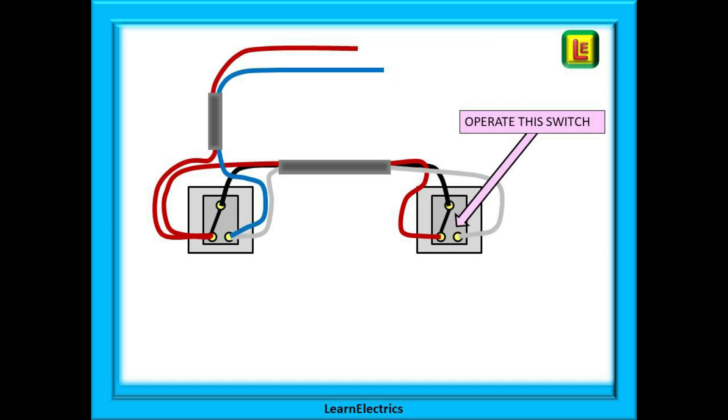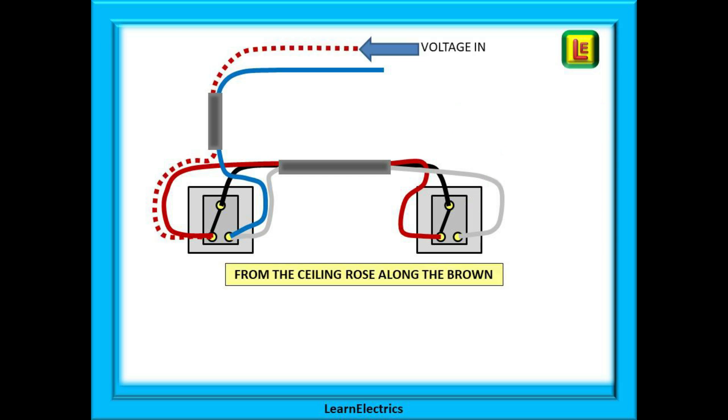If we operate the second switch, shown on the right here, what will happen to the voltage and the current flow? Voltage enters the circuit on the brown of the switch wire as before and goes to terminal L1. Through the switch and along the black to terminal L1 of switch number 2, back along the brown wire to terminal L1 of switch number 1. And the voltage cannot get to the blue wire in terminal number 2, so the circuit has no continuity. This means that there is no voltage coming out of the circuit and therefore the lamps will not light up. No continuity, no voltage, no light.